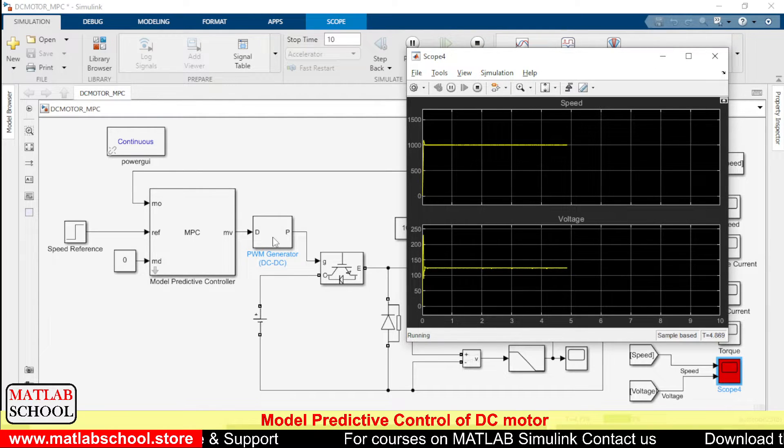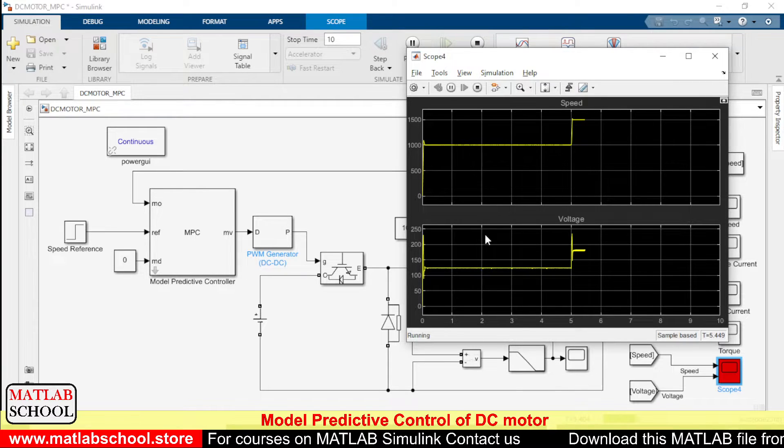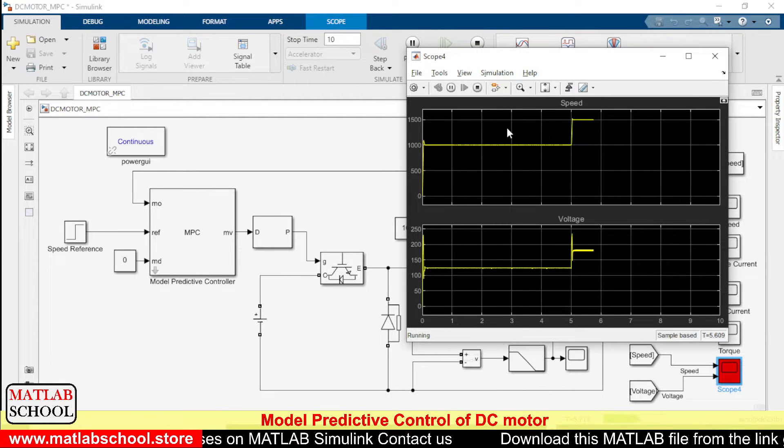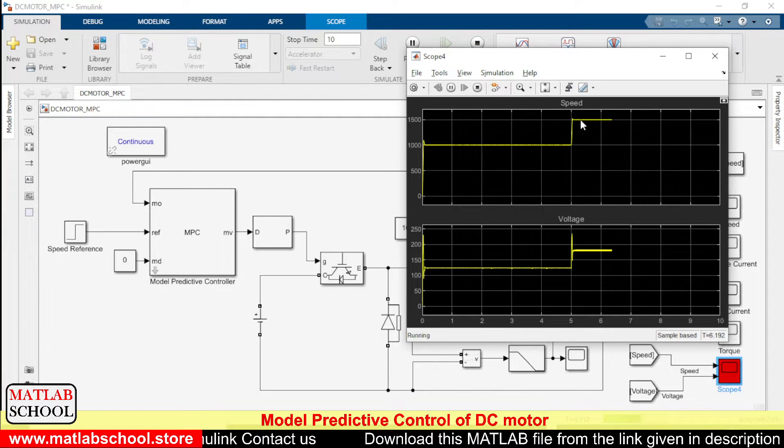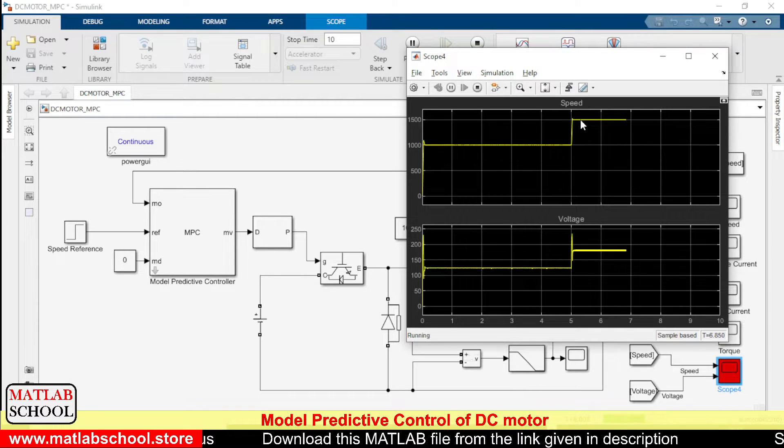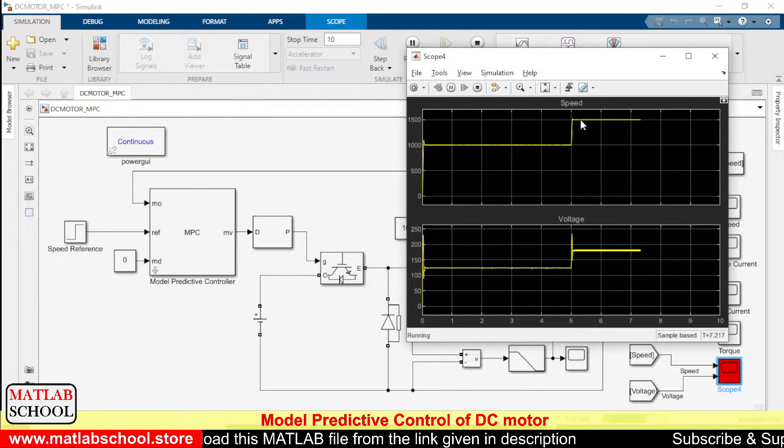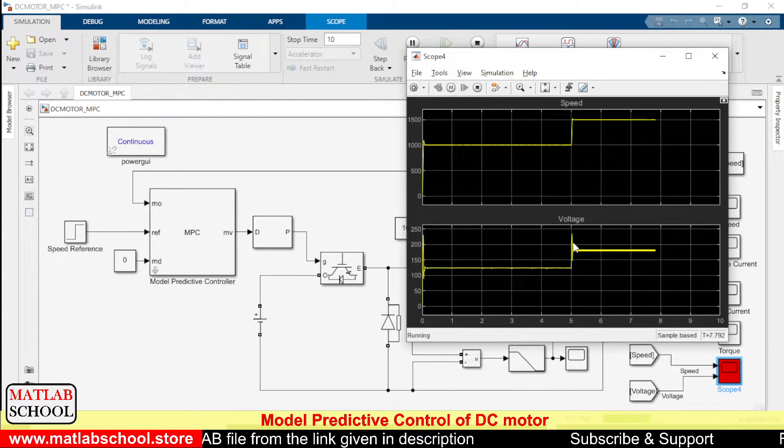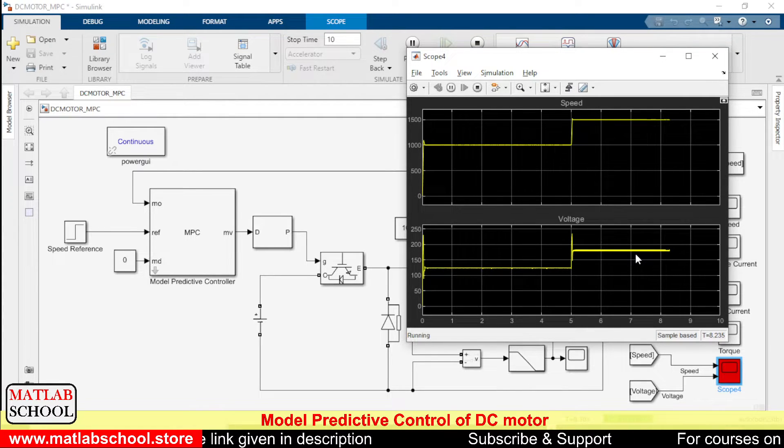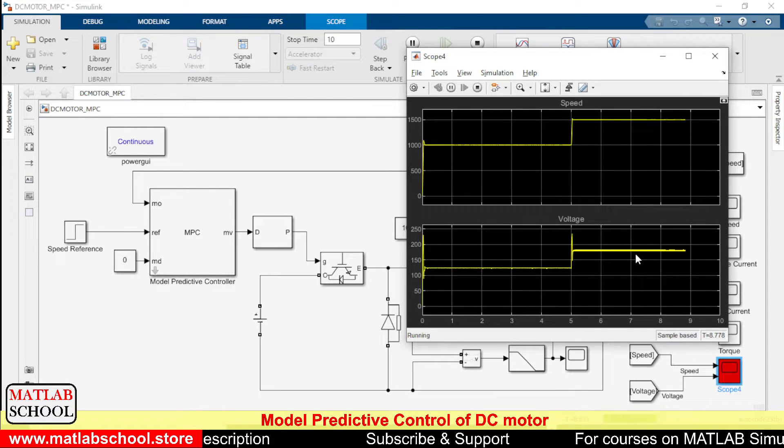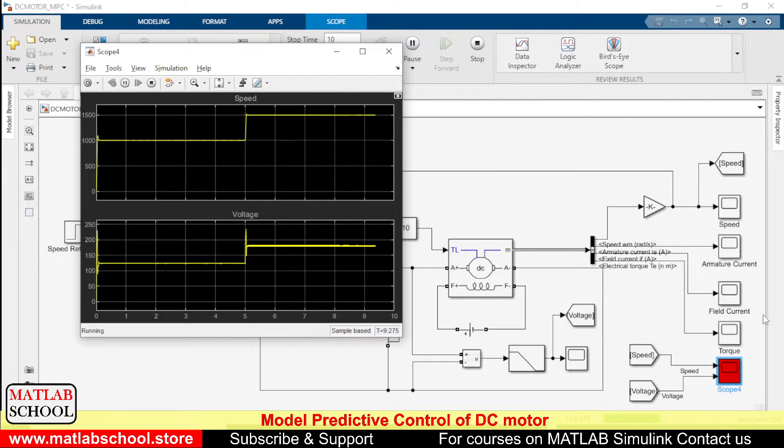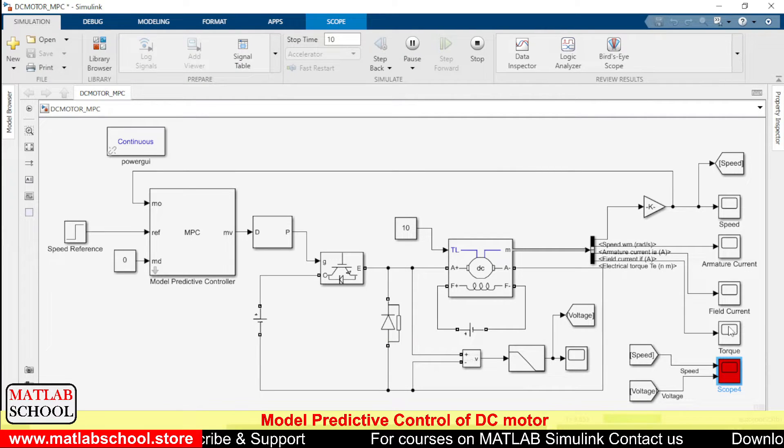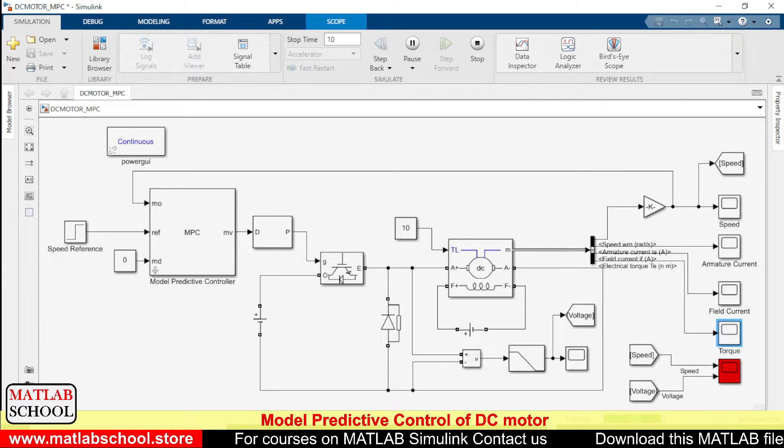So yes, as you can see, the speed is getting settled at 1500 rpm, and the corresponding voltage for 1500 rpm is around 175 volts.